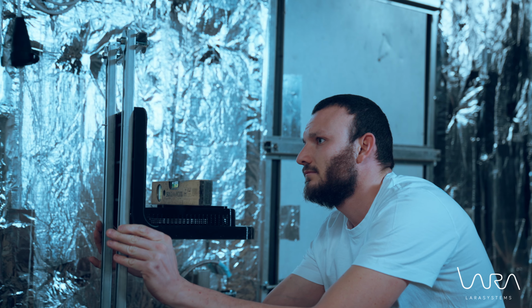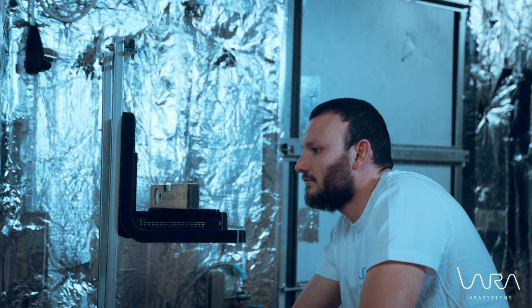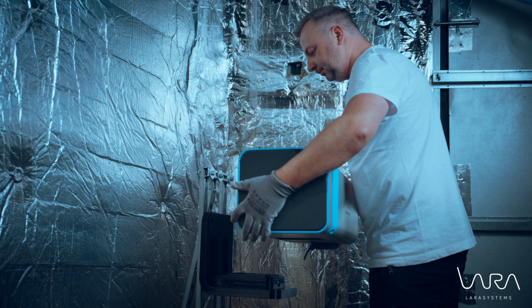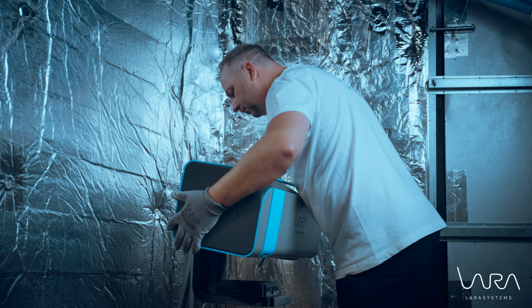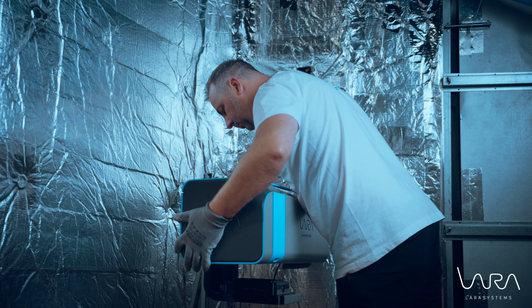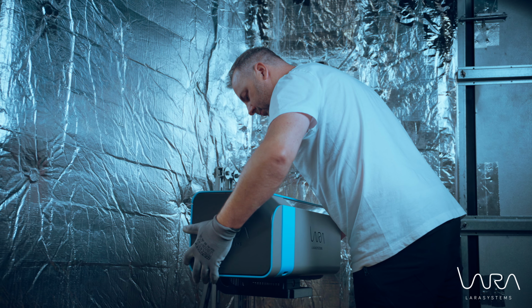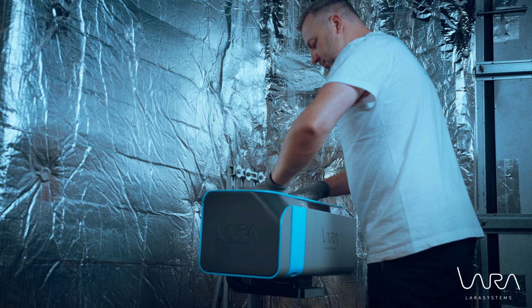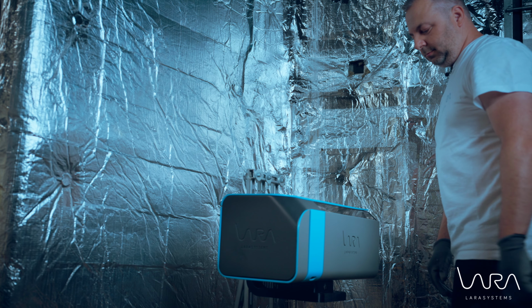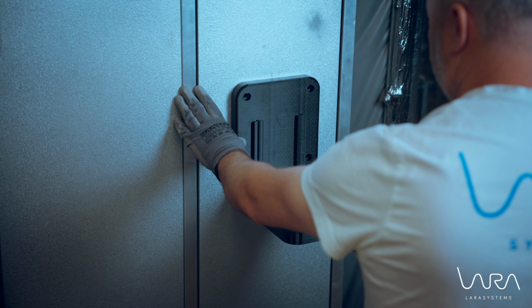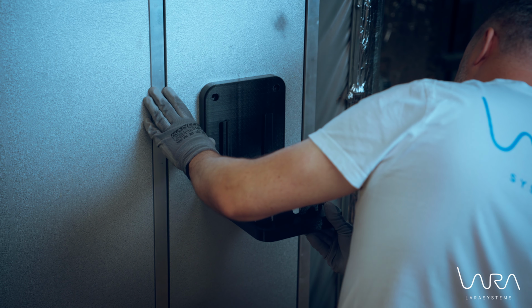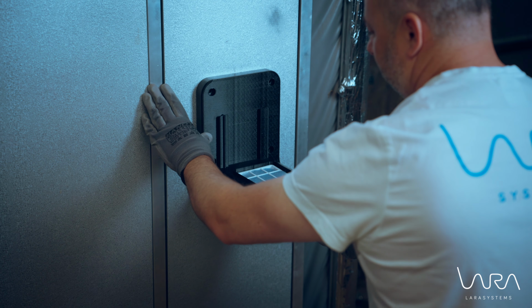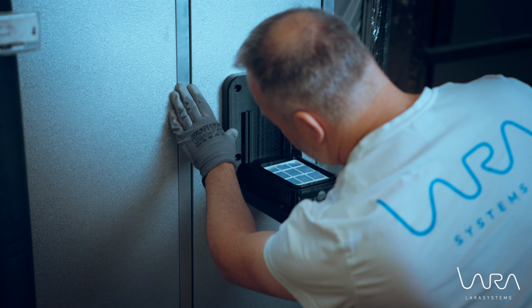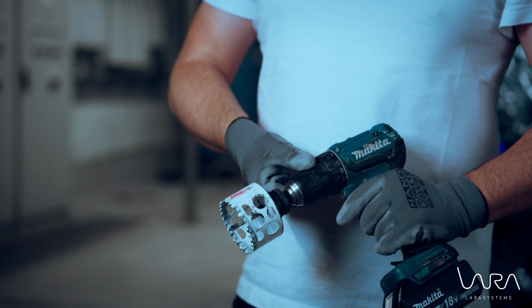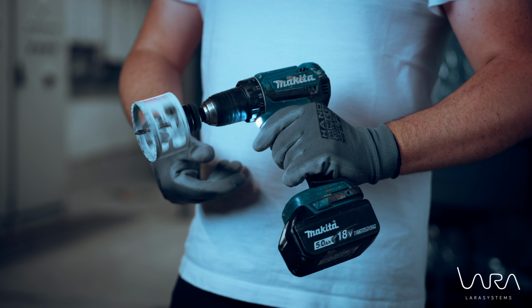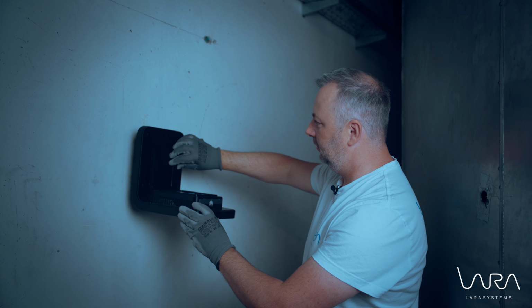If you want to mount the device on the side of the air handling unit, the procedure is fundamentally similar, but in this case, there is no need for the separate accessory stand. Before mounting, always open the doors of the air handling unit and thoroughly check that there are no parts, wires, filters, heat exchangers, moving elements, or maintenance areas behind the chosen surface that would be endangered by drilling or mounting. Only start drilling the device into place once you are convinced that the installation can be performed safely.